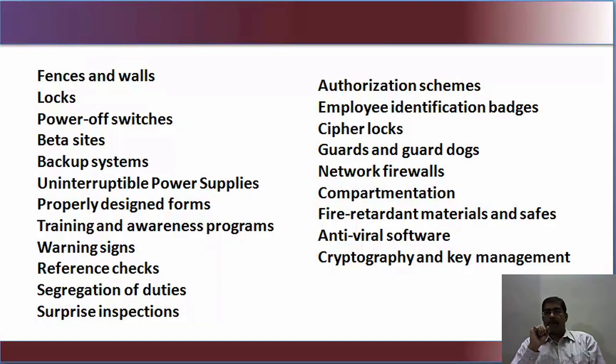So you try to assess the physical security by checking whether the guards who are manning the building are entering the details properly, whether any unauthorized entry can happen, whether proper visitor identification badges are being issued, how long the pass is valid for the person, whether your mobile phones, cameras, laptops are allowed inside the data center.